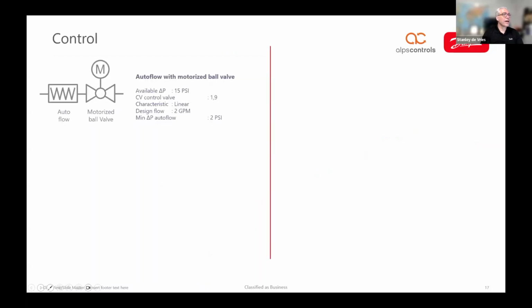Good. And then, because I'm a bit of a nerd, I also wanted to go through some technical things, just shortly, and also why I don't like auto flow or circuit setter solutions with control valves, if you want to modulate. If you do on off, then it's fine. But the autoflow actually destroys all the authority that the control valve has, and I can explain this with an example. Let's say we have a control valve with a circuit setter here. The design flow is 2 gallons per minute.